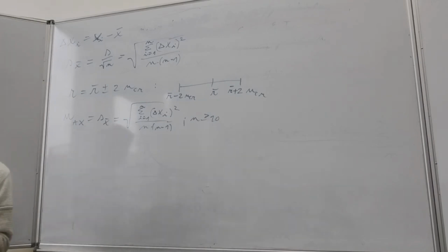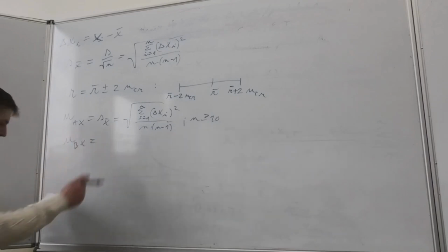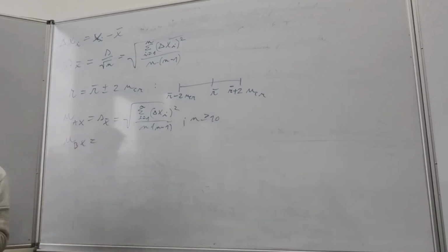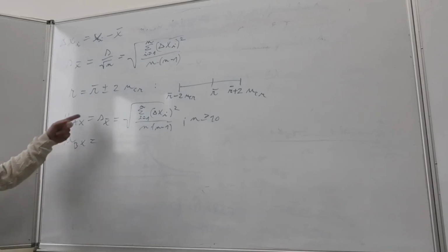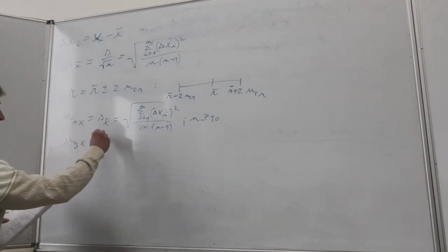Then we have the standard uncertainty of type B. It is obtained in a different way than the standard uncertainty of type A. Its value does not depend on the number of repeated measurements. Its cause is known or identifiable sources. For example, the imperfection of the used measuring instruments, their limited accuracy, and imperfection of the used measurement method. So the uncertainty of type B relates to systematic errors, and the uncertainty of type A relates to random errors. The uncertainty of type B is calculated like this.